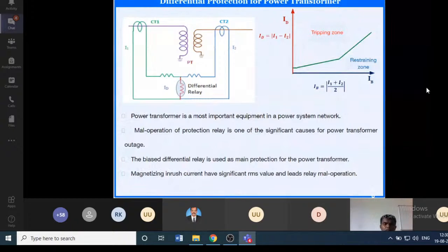The differential protection can be applied for the power transformer. It compares the two currents, the primary and secondary current. The real challenge is associated with the inrush current. When you have an inrush current of significant magnitude, it can lead to maloperation of the biased differential protection. To eliminate this, we are going to use some transformation techniques.